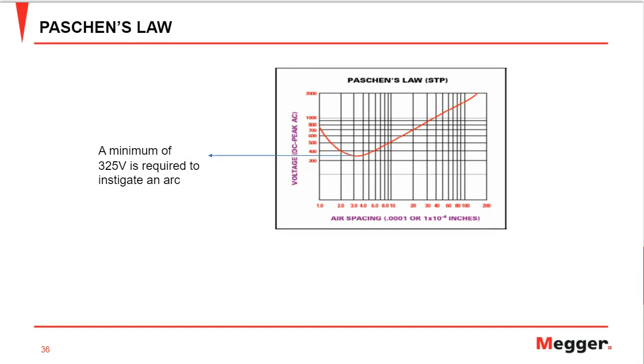And again, that is one of the reasons why the megohm test or low voltage testing cannot find the issue, because of the DC voltage distribution. This law also gives a good reference on why DC hipot testing and surge testing are necessary. And of course, the standards help us understand why those tests are not destructive. So moving ahead, we'll see the principles of surge testing.